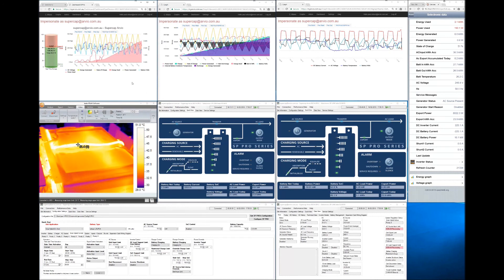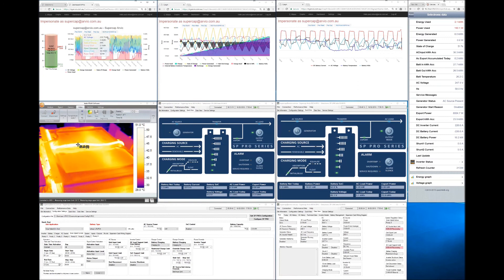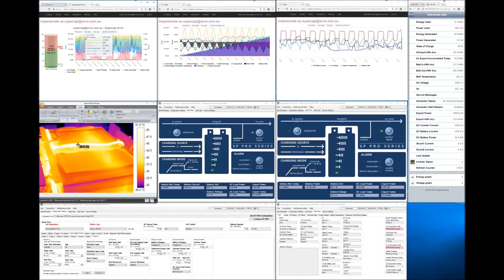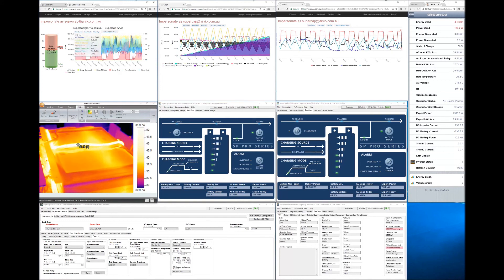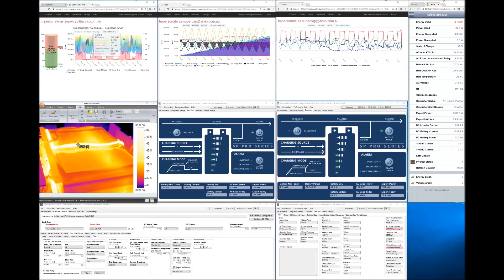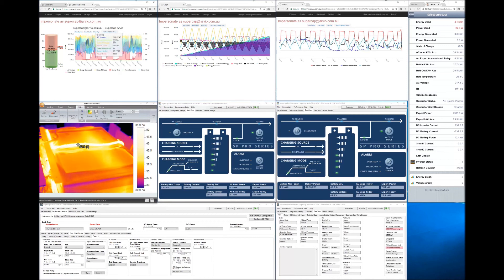We'll just expand out here to a week of time to see what's happening over a larger period. You can see here we've been running this unit I think 14 charge cycles per day for a few months now. And you can see here as I drag the mouse along that we're going up and down, up and down, discharging, recharging, discharging, recharging at around about a 45 minute interval. And there's no loss of performance. So the supercapacitor doesn't lose power over that period.